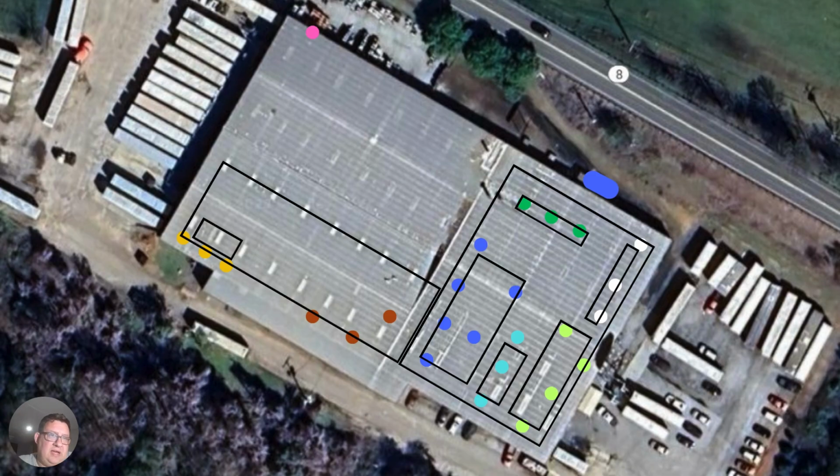So I hope this does a better job of explaining loops and sublooping. I will tell you, especially if you use receiver tanks on these subloops to cover the cycle, you'll see that you'll get a lot less fluctuation at the compressor station to the overall system because that is eaten up by the individual subloops.